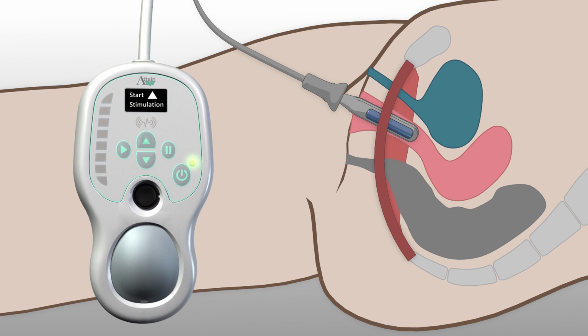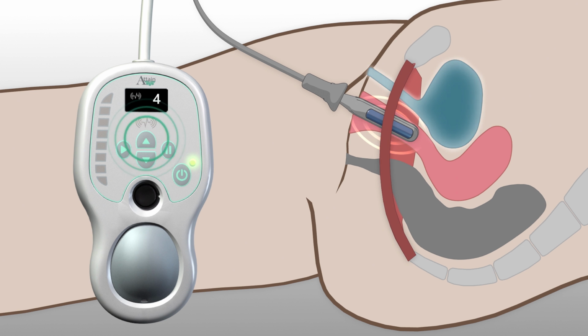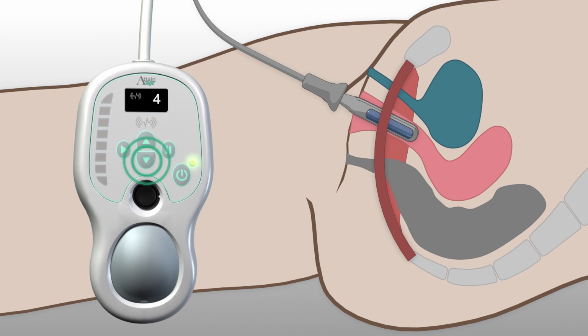Press the up arrow to begin setting stimulation level. Begin at level 1 and increase stimulation slowly, pausing a few seconds at each level until you feel a comfortable full muscle contraction. Your pelvic muscles will contract around the probe and feel as if they're pulling upward and inward. At any time the sensation feels too strong, you may use the down arrow to decrease stimulation level.